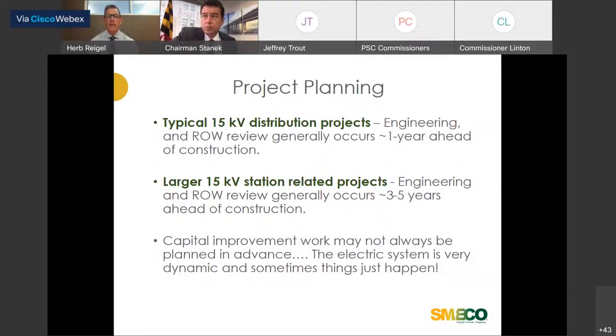It's important to realize that capital improvement work may not always be planned in advance. The electric system is very dynamic, and sometimes things just happen. Two examples come to mind: a seemingly healthy substation power transformer with good reliability and maintenance records may, for some unbeknownst reason, suddenly experience an internal fault and need to be quickly and immediately replaced. Another example might be a large commercial project that materializes in the service territory and requires upgrades to the distribution system that were not previously included in a planned work plan.